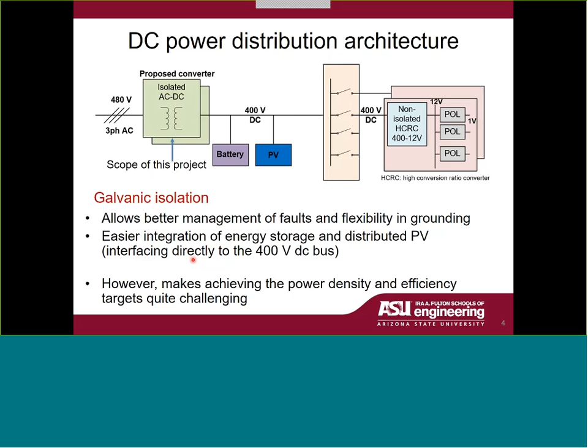If you operate directly from 13 kV, isolation is no longer a choice, it's a requirement, because with such a high voltage conversion ratio from 13 kV to 400 volts DC, isolation is the best choice. Having outlined all these benefits, the need for a high frequency transformer is what makes achieving 98% efficiency and 150 watts per cubic inch power density extremely difficult, and that's something we are addressing through a combination of topology, silicon carbide devices, and much improved magnetics.